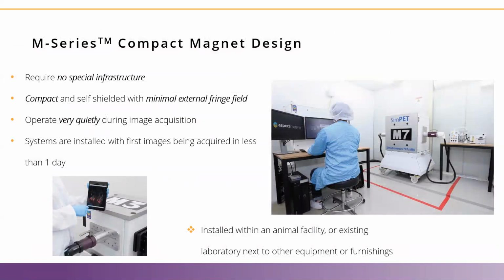What makes this system unique is that it is a compact permanent magnet that's self-shielded. And so being a permanent magnet means that once the neodymium, which is the material that the magnet is made of, is magnetized in the field, there's no electrical requirement to maintain the magnetic field. And so with that, there's no heat being generated, so there's no heat that needs to be dissipated. And so other systems that may be available in the marketplace, you either have to have cryogens like liquid helium, or a tremendous amount of water to dissipate that heat. And that's a bit of an infrastructure requirement to allow that heat to be dissipated.